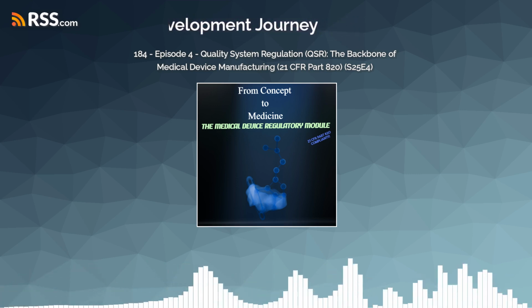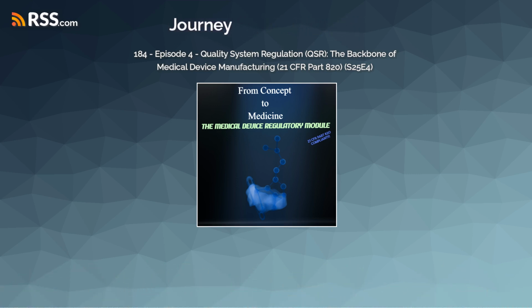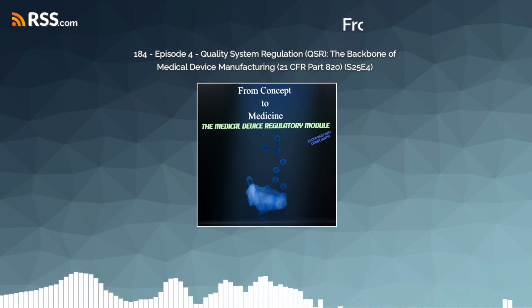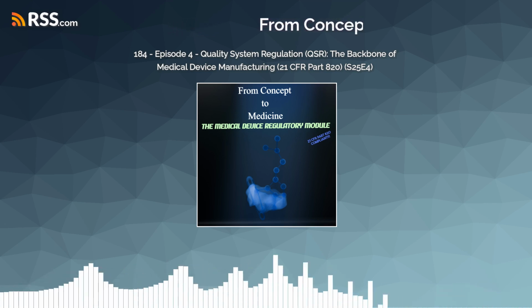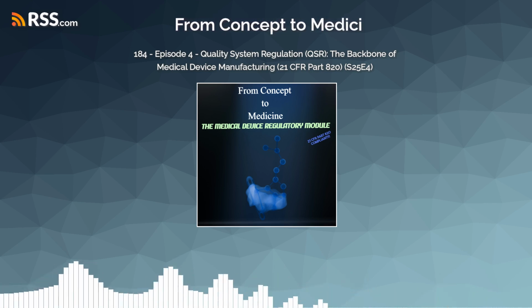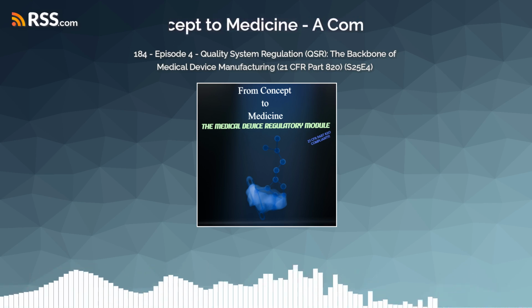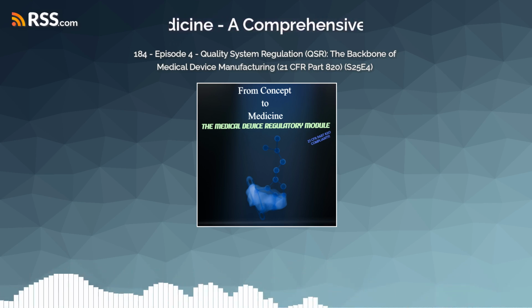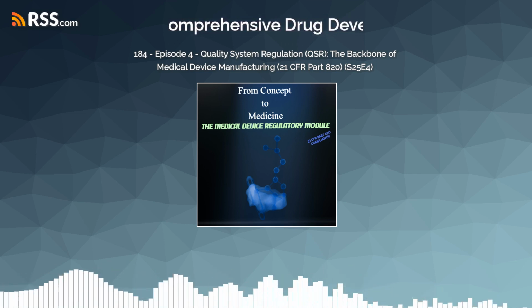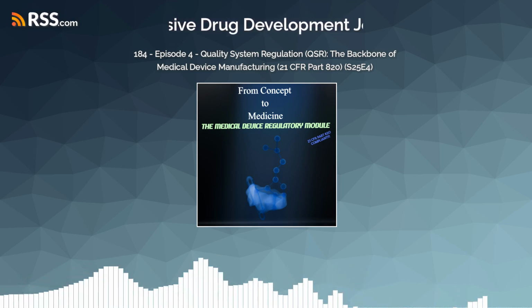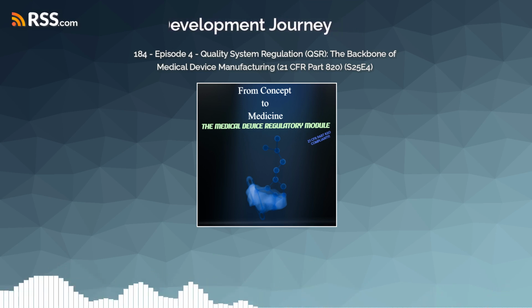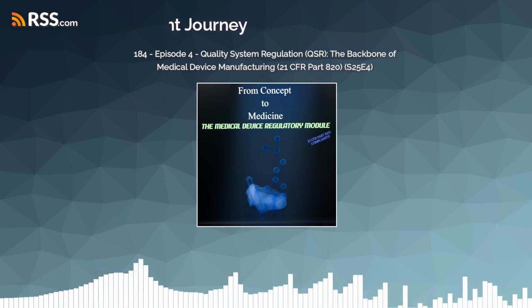Makes sense. And tying all this together is risk management. Yes. Risk management shouldn't be a separate activity you do once. It has to be woven into everything: design, manufacturing, supplier selection. It's about proactively thinking, what could go wrong here? How likely is it? How bad would it be? And then what controls can we put in place to reduce that risk? That's continuous. It has to be.